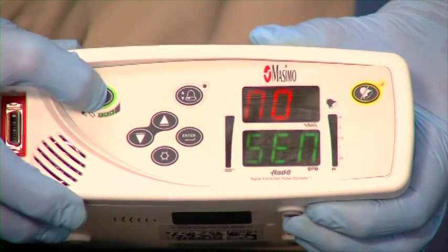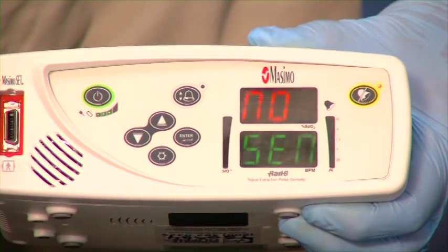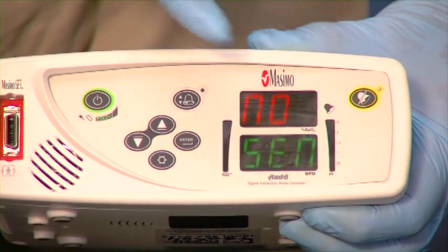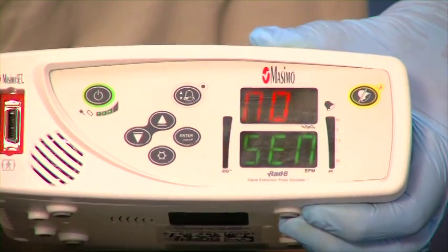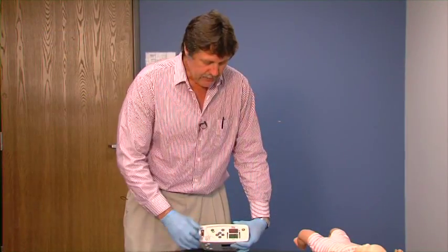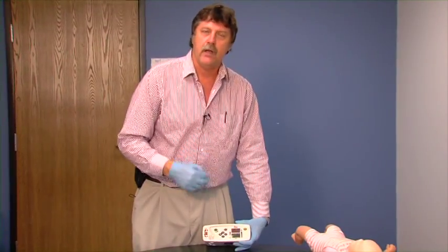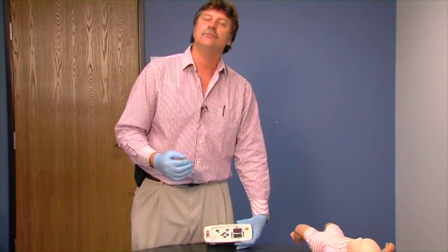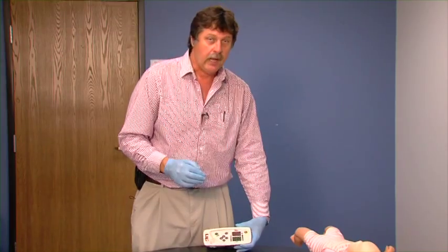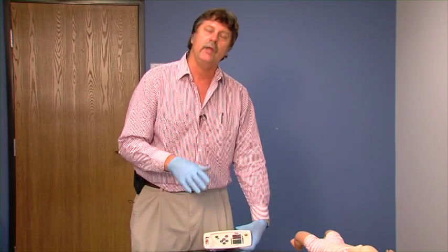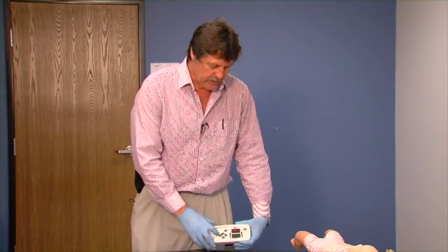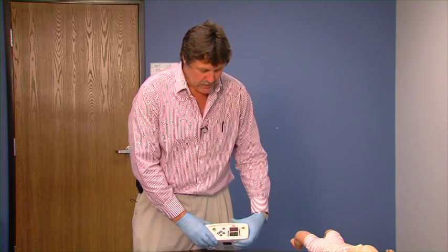Press and hold the on button till the machine comes on. Okay? Right now it's saying no send because we don't have any sensors hooked up to it. But we want to program in our values, and those values should come from the doctor. However, if they don't, we do have default values that we can program into it.